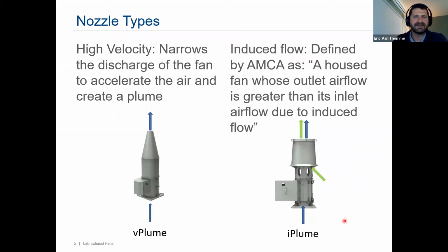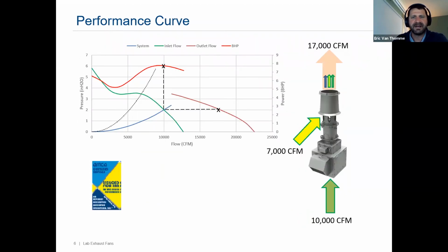And so AMCA went ahead and created a certified ratings program. I'll show that on the next couple of slides here. It is additive, but it's difficult to measure. And so what AMCA did is come up with a certified ratings program. I'll talk about the testing in the next slide, but essentially it's 10,000 CFM coming through here, and you have 7,000 coming through the induced flow area of the fan. You get 17,000 CFM coming out.